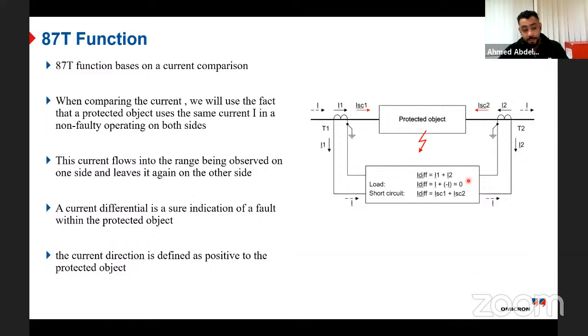Let us say in case I have a faulty condition, what will happen? I have I short circuit 1 flowing inside the protected object, and I short circuit 2 is also flowing inside the protected object. So this will be positive, this will be positive, and we don't know the contribution from this side and the contribution of this side, because it depends if I have a load here or only an infeed. So in general, in the short circuit case, the I differential will equal I short circuit 1 plus I short circuit 2, which can give me a significant value. In the ideal case, I short circuit 1 will equal I short circuit 2, and we will give them a general name, I short circuit. So the differential current will be 2 I short circuit.